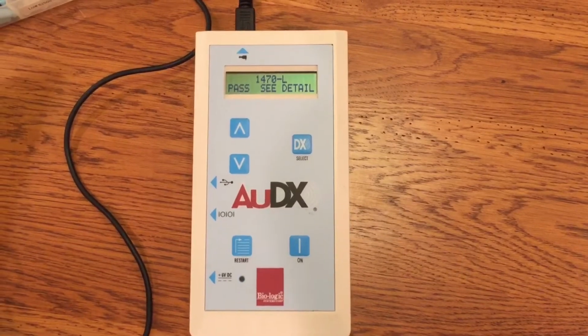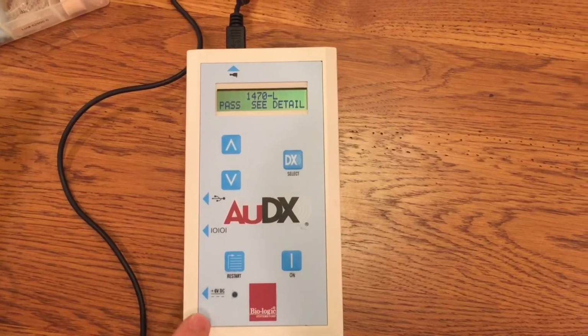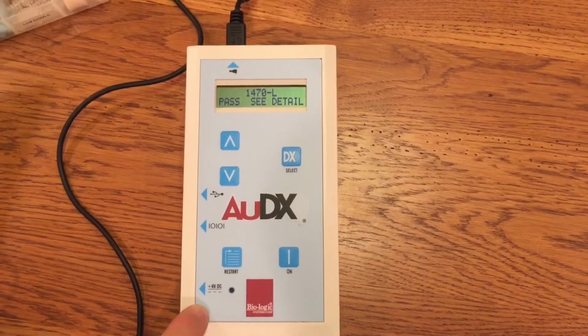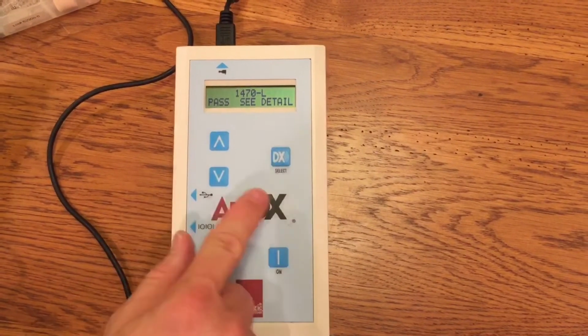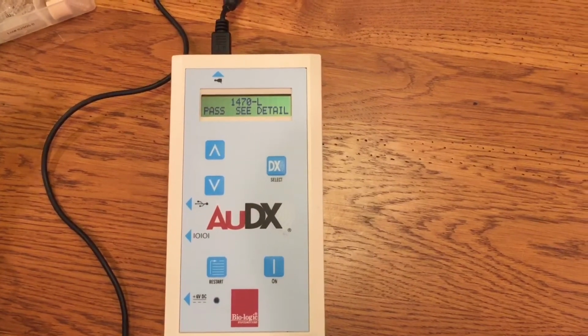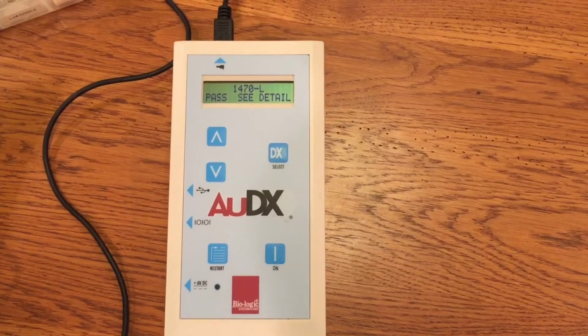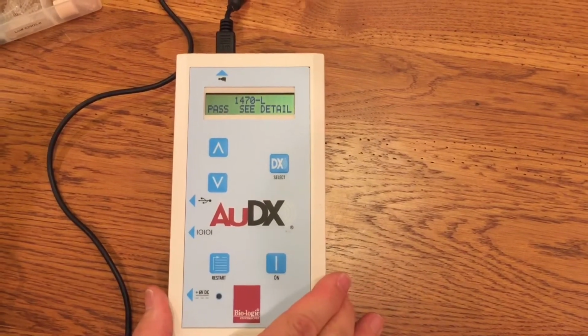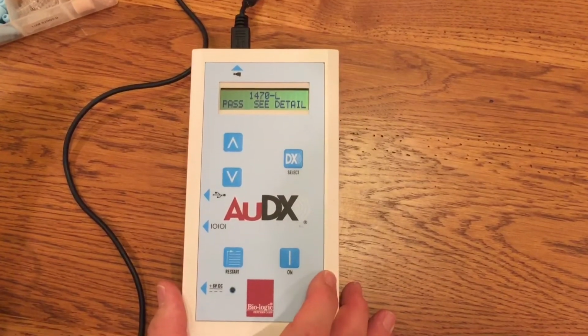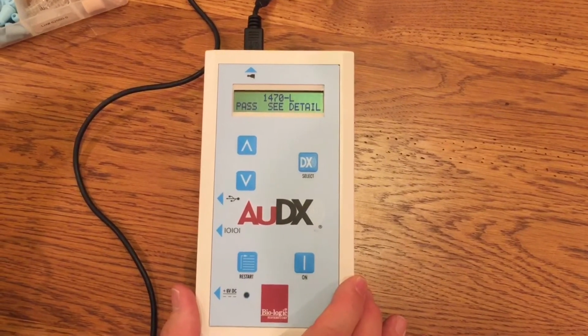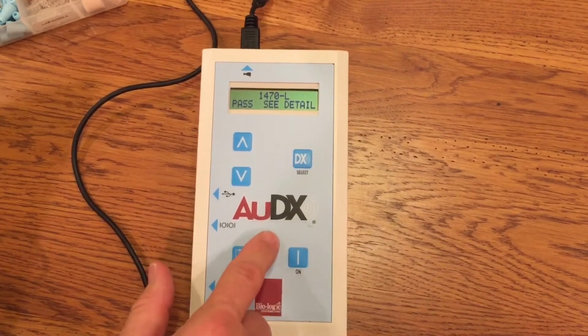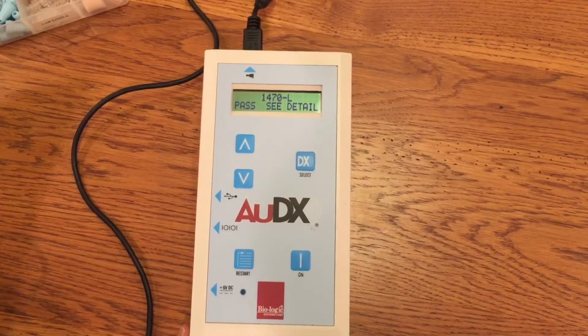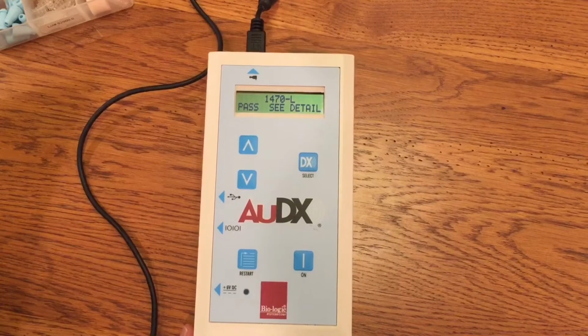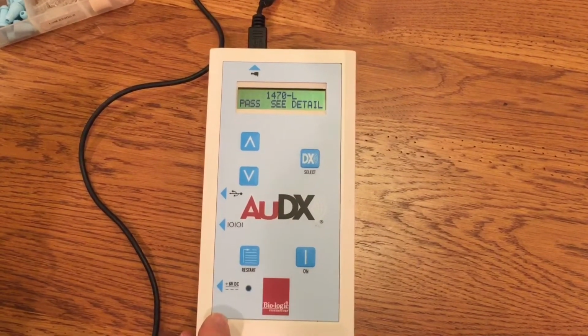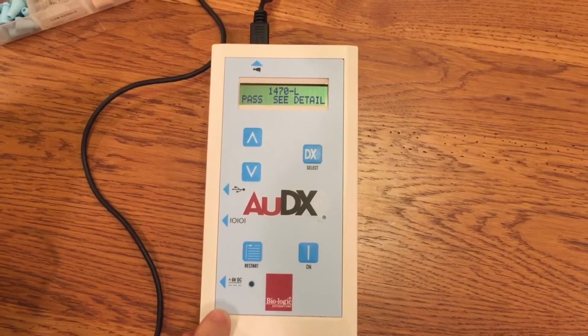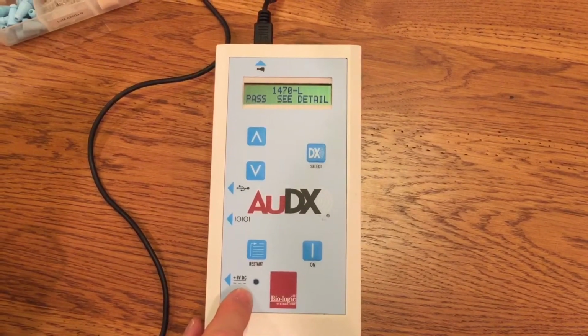Okay, some other things just to remember is that the AUDX, or the unit, turns itself off after 3 minutes, so there's no need to turn it off, and there is no off button. In regards to saving a result, the machine will automatically save the results of completed tests. Depending on the machine that you have, it'll save a minimum of 25 tests and up to several hundred. So remember the rule of 3. 3 hours to fully charge, and then 3 hours of continuous testing before it needs to be charged again, and then the machine turns itself off again after 3 minutes. And also, again, remember, you can test with the unit plugged in to the wall.